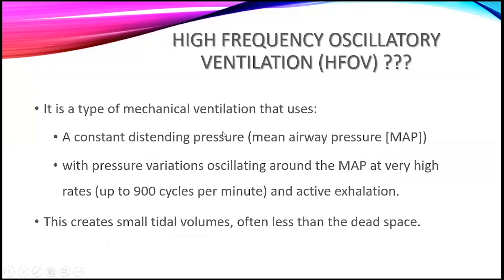High frequency oscillatory ventilation is a type of mechanical ventilation totally different from conventional ventilation. It uses a constant distending pressure called the mean airway pressure — there is no PIP, only mean airway pressure throughout the entire ventilation cycle. The ventilator delivers pressure variations at very high rates, producing very small tidal volumes equal to or less than dead space, and is characterized by active exhalation. There is constant distending pressure with oscillation around this mean airway pressure.